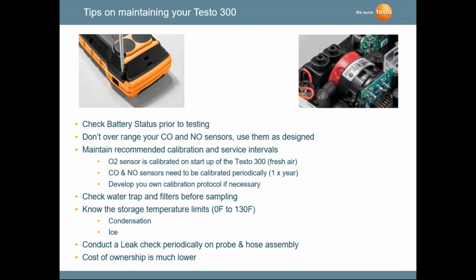Check water traps and filters before sampling. At the probe handle, there is a filter, and that can be easily changed out when they get dirty. They're white filters, and when they turn black, it's as simple as that. You just unscrew the cap, turn the cap counterclockwise, take out the filter, put in a new filter, and you're ready to go.